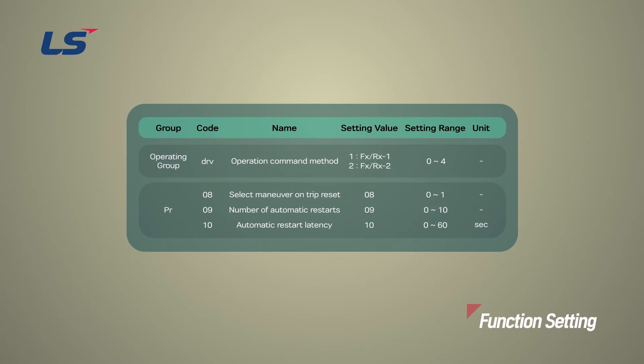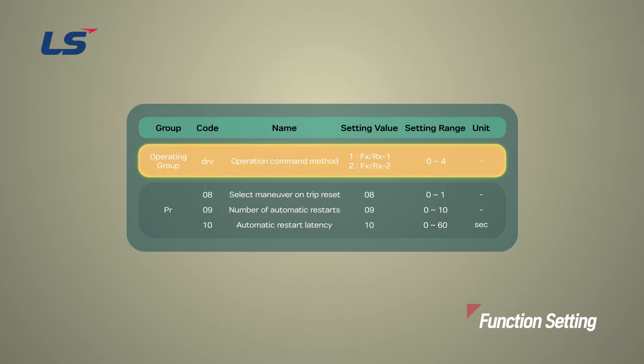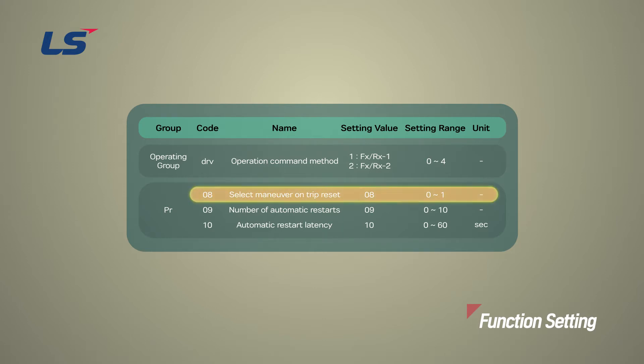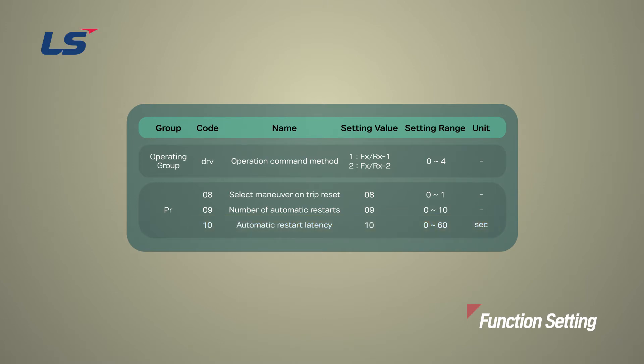Let's see how to program the Reset-Restart function. In order to use the Reset-Restart function in G100, the command source in the Operation Group parameter must be set to the Terminal Block Operation command method of number 1 (FX/RX1) or number 2 (FX/RX2). Next, set PR group number 8 parameter to number 1 (Yes) to activate the Reset-Restart function. After setting the number of restart attempts in parameter 9 of PR group, set the restart delay time in the 10 parameter of the PR group. All settings are entered to enable this function.